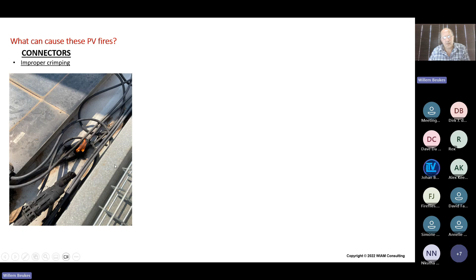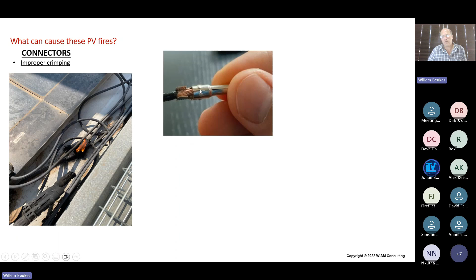In most cases, the wiring goes into the tube cylinder of your MC4 connector, where they didn't cut off the electrical wire on the wings of the connector. And then there's a constant arc forming between the wire and the pin connector of the MC4. So it's an electrical installation problem, where the equipment hasn't been installed correctly, and these MC4 connectors then start to arc due to the shortest path the electrical current will flow. So the first level is to make sure that these connectors are installed correctly. Here's a video of an installer not doing it right, and you can see on this video where a lack of proper installation can cause these arcs to happen.